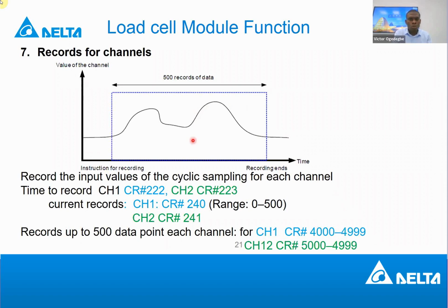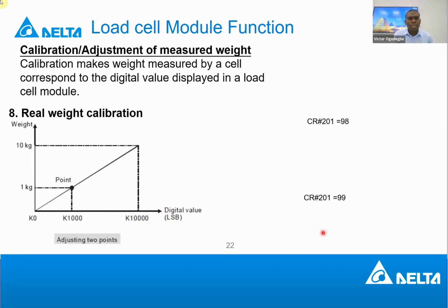Maybe your weighing machine is connected to an HMI. The HMI can read the PLC address that is reading this, and then you can plot a graph with it on your HMI. So what you do with this data is flexible, but this helps you to keep track of what you have measured. The load cell itself cannot keep a record. It just measures the weight that has come. The load cell or the sensor has forgotten, but the module keeps track of what has been recorded. So it can record 500 different numbers and keep them in the stack for you. You can use those data to make some analysis, depending on the kind of machine that you have.